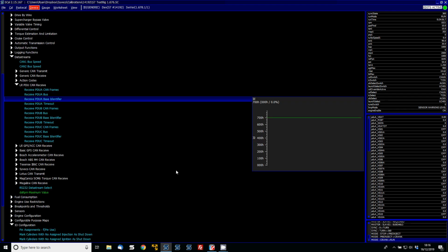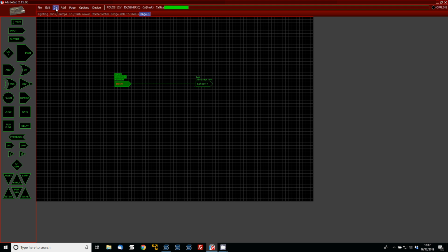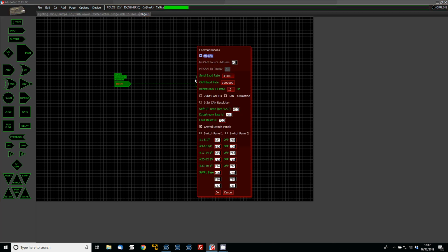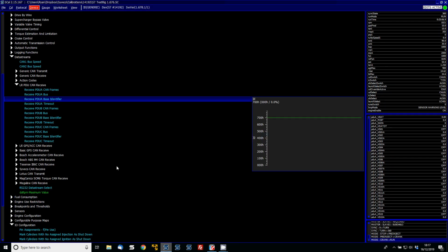In the CAL communication area, you can see the data stream base ID is 700. That's the default value, and the value in SCAL will generally match that. You probably don't want to change that, but if you have something clashing with that 700 on the bus, then you can change it.